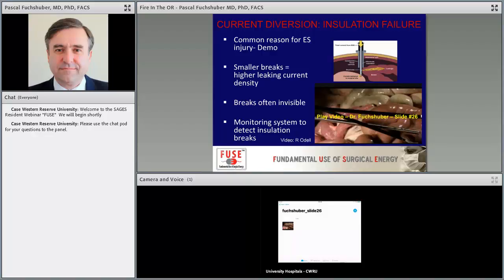insulation breaks. So with regard to insulation breaks, really the word should be, you have to assume every time you use a long-shafted insulated instrument in laparoscopy, you have to assume that this instrument has insulation breaks and use it accordingly. In other words, you need to understand where it is, what it is touching, and when the energy is being applied, that it doesn't touch anything you don't want to touch because there could be a break.